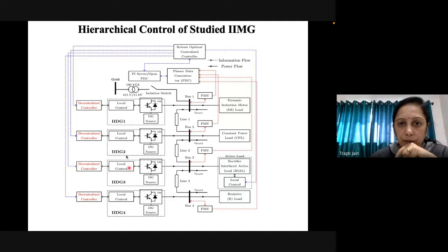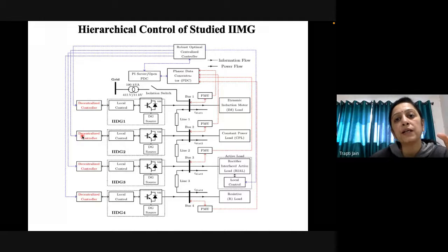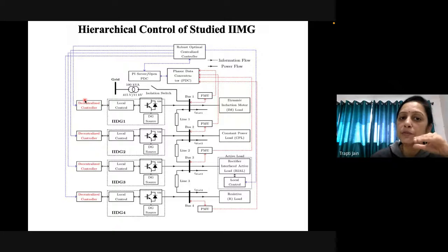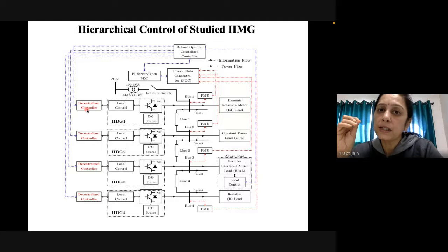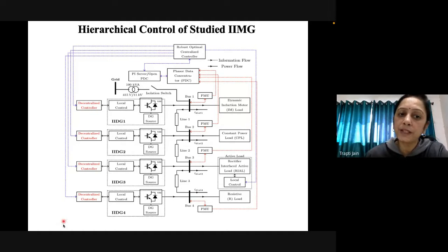The advantage of this controller is that if the centralized control fails, the decentralized control will still be able to maintain the stable and basic operation of the microgrid. But the centralized controller improves the performance of this decentralized control. So the decentralized control was developed to ensure stable operation of the microgrid, and the centralized controller is used to enhance the performance of the local controllers. So this is the structure of the control.